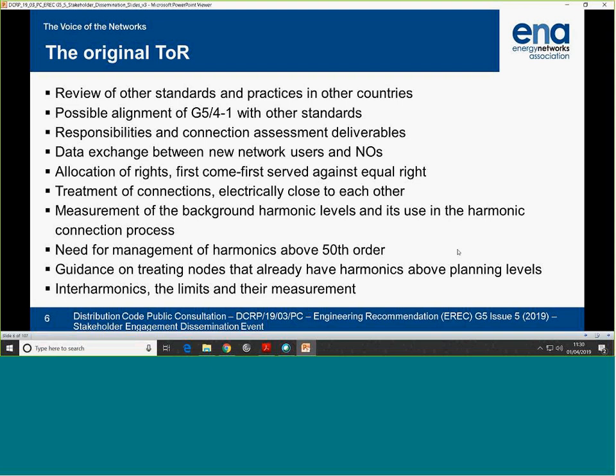There is a working group in IEC looking at this. So, we've been trying to manage harmonics above 50th since 2010, but there was no basis for us doing that. A legal basis. That's not quite right. This is in the grid code, so we use that to impose conditions on connectees. But there was no guidance. That's a better phrase for it. And harmonics in G5/4 was very abstract. So we thought we need to look at that and see what happens because, again, changing technologies.